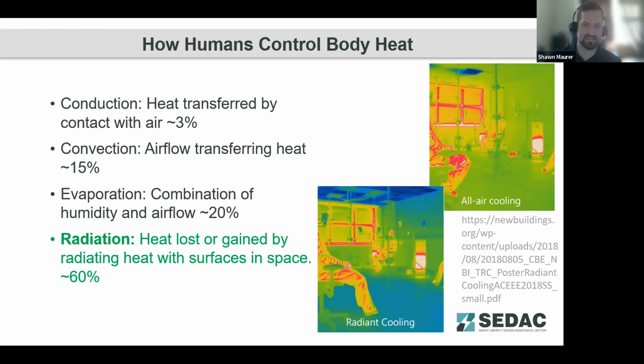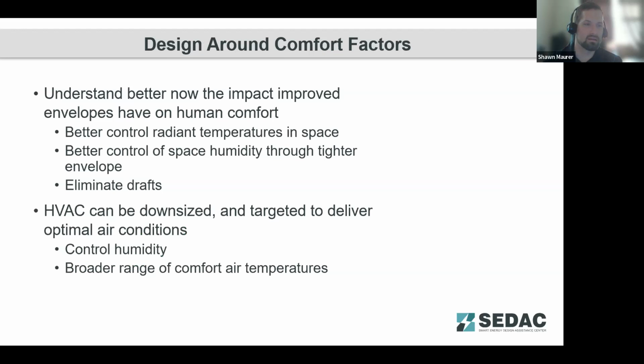Unfortunately, for most building designs, we focus on fully mixed air conditioning. When most people think about making themselves comfortable in a space, they think about going over to the thermostat, turning it down so that the air temperature changes. Where radiant systems can definitely provide much more comfort at much less energy consumption than air conditioning systems. So this is also why it's important to focus on the envelope, going back to that initial design. Improved insulation of windows and walls, getting rid of thermal bridges is going to maintain that more consistent radiant temperature in the space that we feel more than other conditions in the space. And so you have better control overall of space comfort.